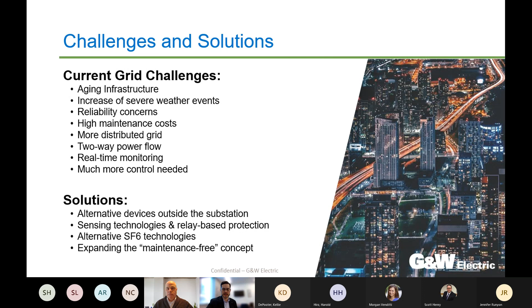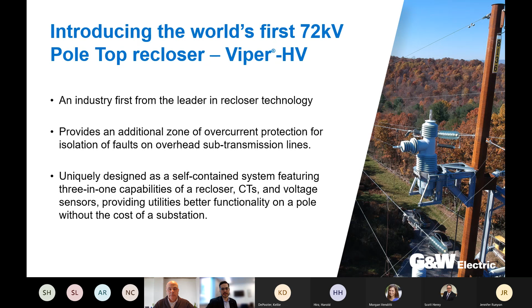So as our owner has already introduced, I'd also like to introduce the world's first 72 kV pole-top recloser, our Viper HV — yet another industry first from G&W Electric. The Viper HV provides an additional zone of overcurrent protection to isolate faults on overhead subtransmission lines outside the substation. It's a very unique product: a self-contained, 3-in-1 device incorporating the ability of a recloser along with embedded current transformers and voltage sensors. This gives utilities better functionality on a pole without the added expense of building a brand new substation.